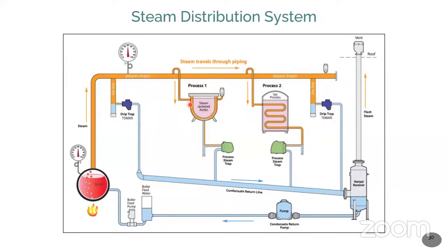Then once you use the steam, whether it's direct heating or indirect heating, automatically it starts to condense, and the condensate can be properly removed with the help of a pump or traps. Sometimes you have traps, and the trapping system lets the water out, and the water will be connected to the condensate return pipe. Okay, now you see the process will have a trapping system. For condensate recovery, we have a separate pipe, and that should be connected to the condensate system. So in that way, we can collect all the condensate.